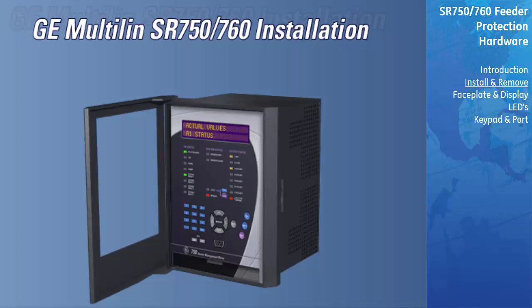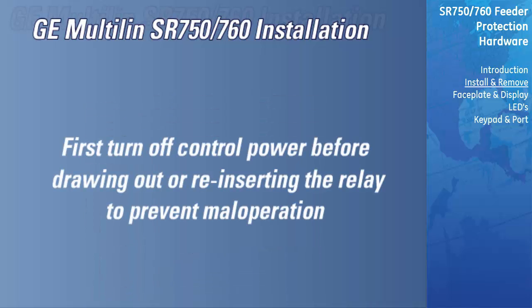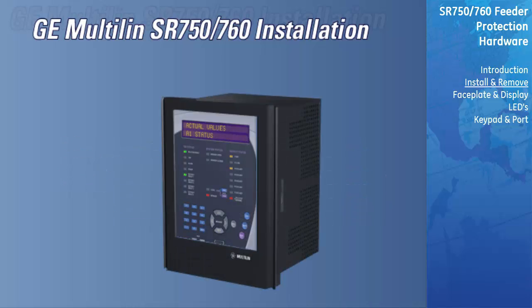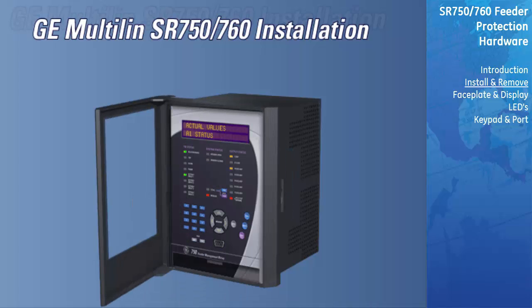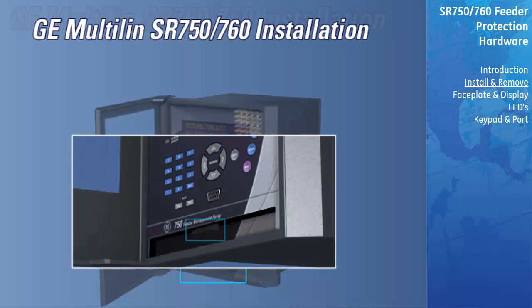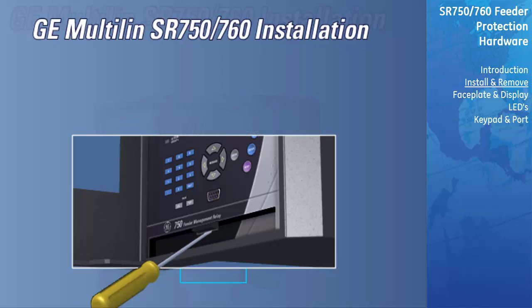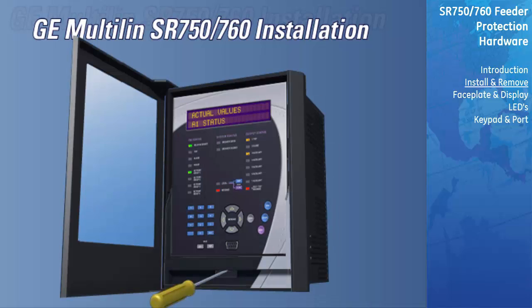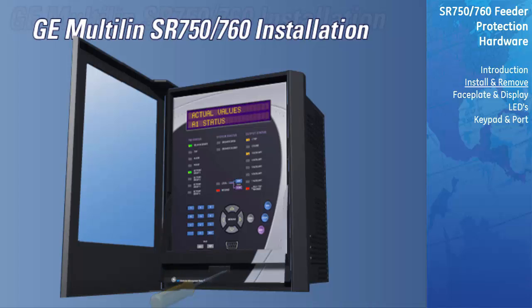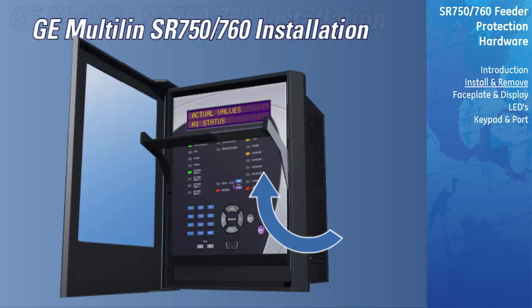To remove the unit from the case, first turn off control power before drawing out or reinserting the unit to avoid maloperation. To remove the unit from the case, open the cover by grasping the center of the right side. Press upward on the latch, and then pull the front door, which will rotate about the hinges on the left. Release the locking latch located below the locking handle by pressing upward on the latch with the tip of a screwdriver. While holding the latch raised, grasp the locking handle in the center and pull firmly, rotating the handle up from the bottom of the unit until movement ceases.